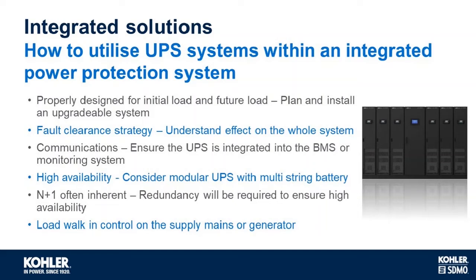One of the things that we do with the UPS is to make sure that we're using the advantages of those modern generators, is make sure we can control the walking of the load onto the supply or onto the generator. And with this type of UPS, we will control that gently so we do not exceed the maximum load step of the generator.